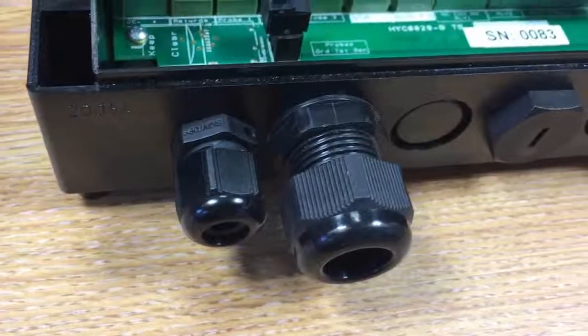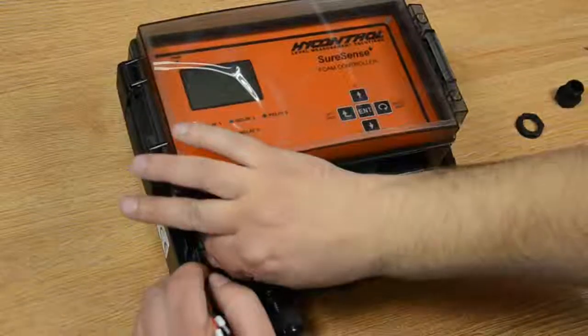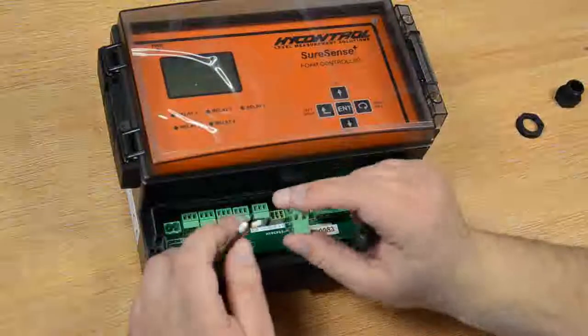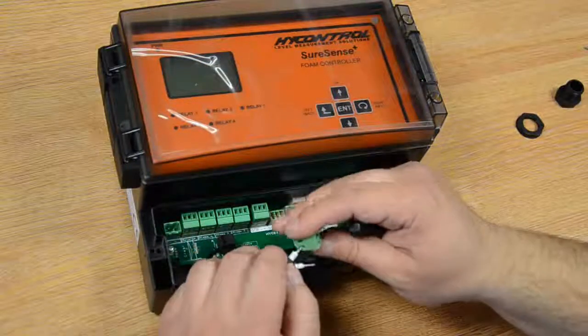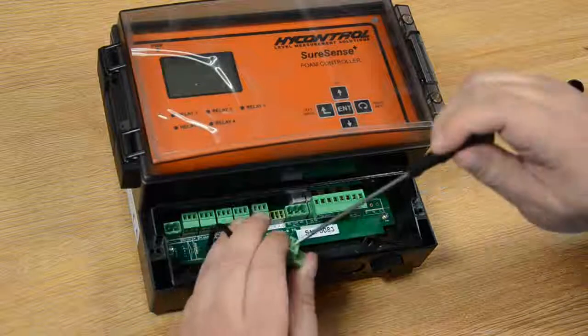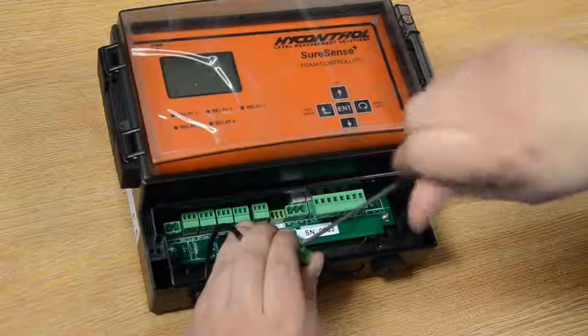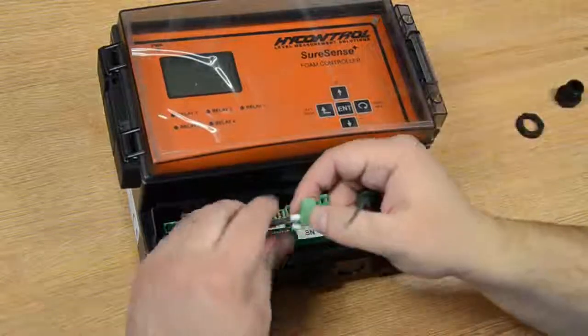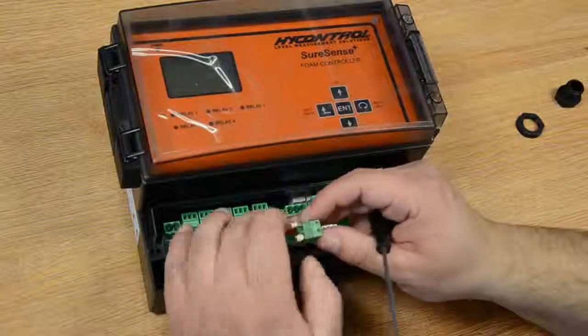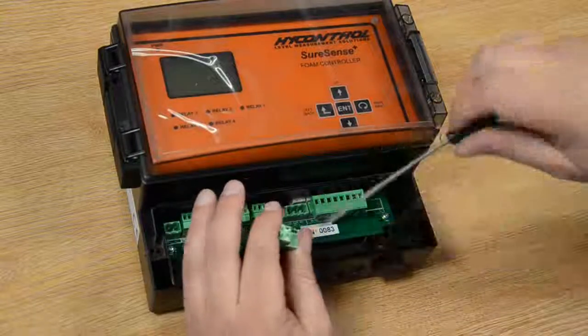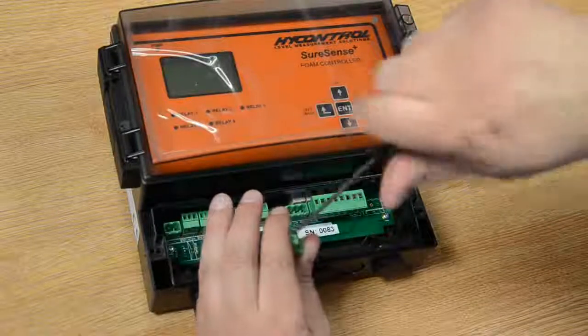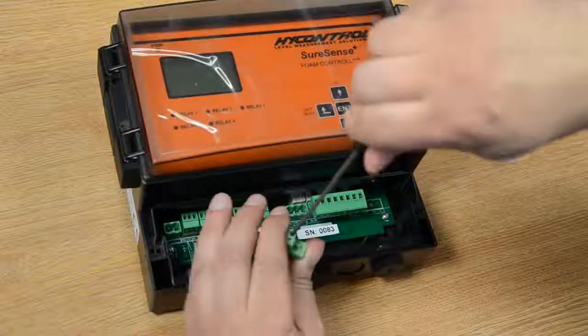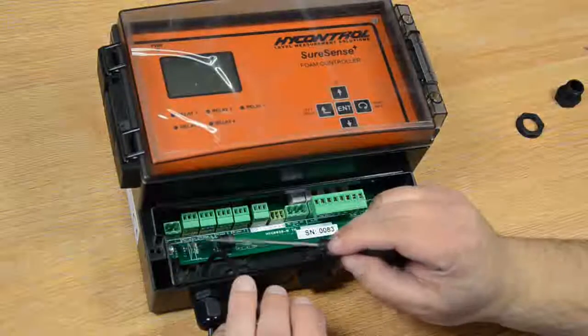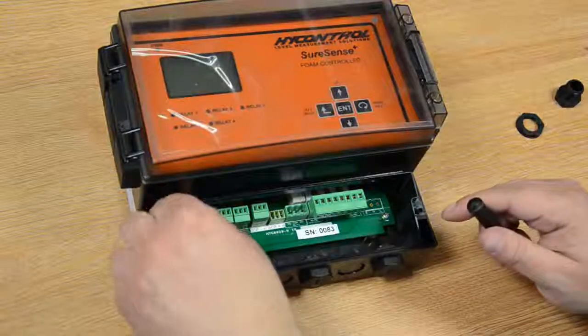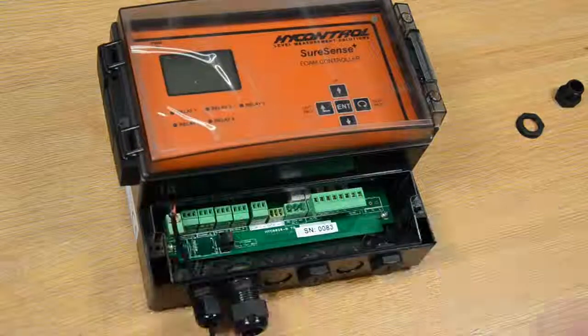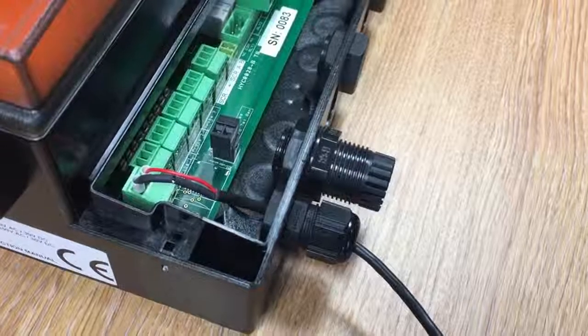To wire up your DC power you need to come through the cable gland, and then you can connect into your terminal block. We wire the negative into our left hand side and make sure it's tight, and our positive to the right hand side. This is also marked out on the board, negative and positive. So we can then put that terminal block back in.